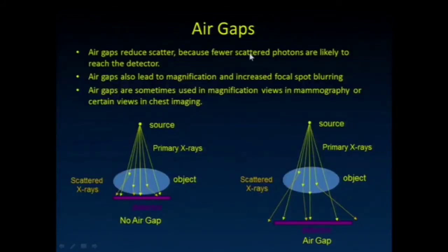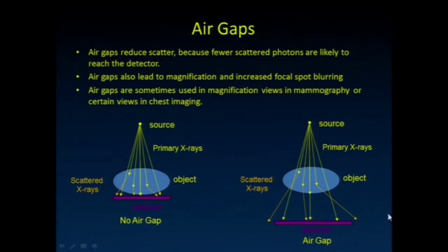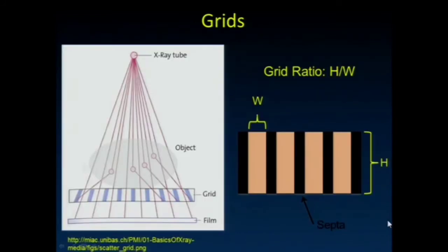Air gaps also reduce scatter. If you move the detector away from the object, you give room for some of these scatter events to escape and not strike the detector. So using an air gap can help. That's why we don't use grids in magnification mammography — because there's an air gap there that already helps keep our scatter down.